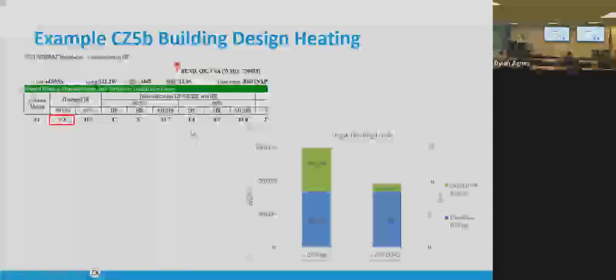This is in Bend, Oregon, about a 6,000 square foot office building. They're a little colder, a little higher elevation than Boise, but other than that, very similar weather. So 5.5 instead of 11 design day. We did load calcs on this building. First thing was crazy. We did load calcs for the existing building with no heat recovery, and we got 180 MBH of design load. And we were being pretty conservative. We weren't trying to get too aggressive. So 15 tons ish.